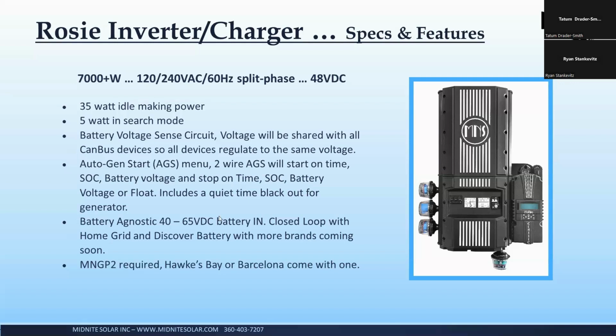We call that the MNGP2, because those of you familiar with the classic, that has an MNGP, stands for MidNite Graphics Panel. So you do need one of those to set up and program the inverter. The Rosie will physically not work for you unless you have a display to program it. You can remove the display and take it with you if you want, but you do have to have that to program it once. And we did that mostly because we found way too many people just pick default values and go, and batteries really, really, really need you to program the proper variables in the equipment for those batteries.